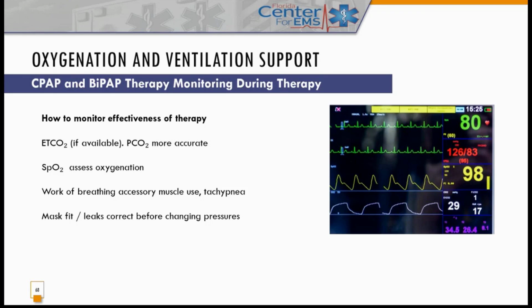Mask fit and leaks should be corrected before changing pressures. That's why that manometer is nice. If I've got an alarm going off, I'm looking for a leak, and if my manometer isn't reading what it was before, I've got to think there's a leak somewhere.